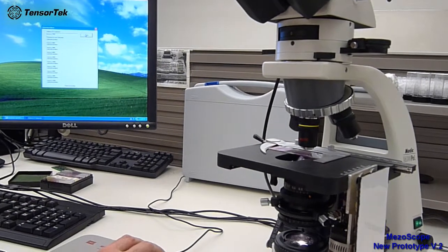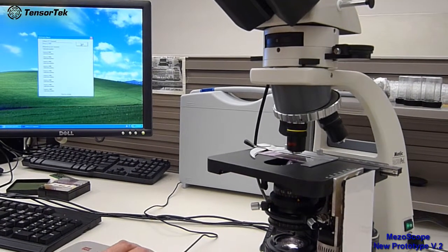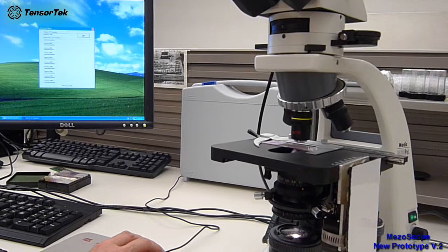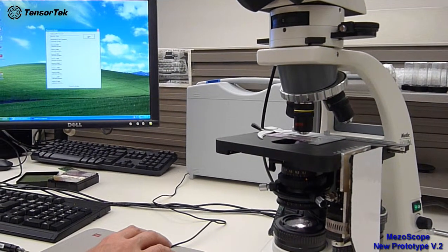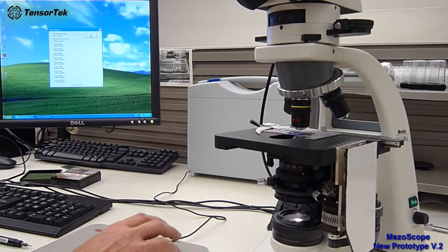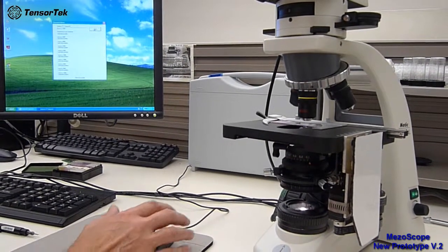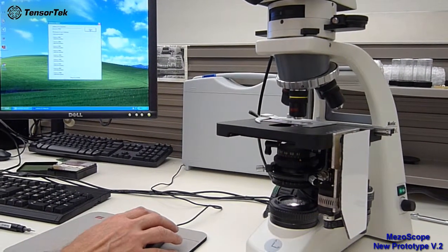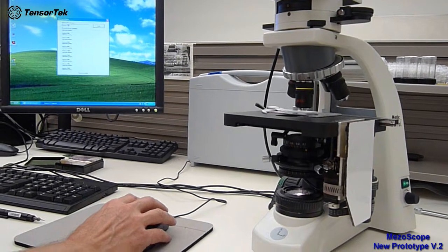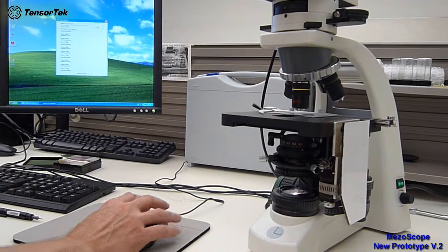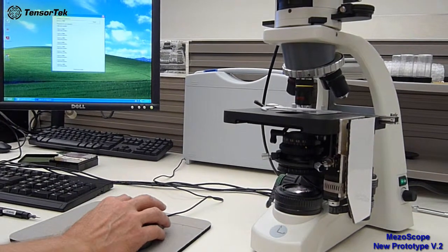It's accurate. The resolution is approximately 200 nanometers, but the repeatability is approximately 5 microns or so, because we're using a belt drive system here. We can improve the accuracy if we want, but we want to maintain low cost for the consumer, or for our clients, that is.